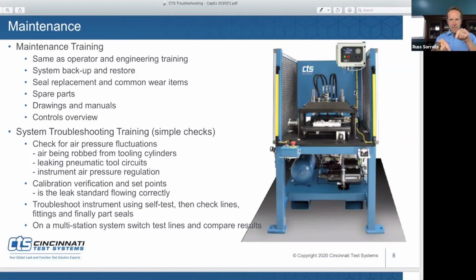Absolutely. Yeah, and it's just chasing it back. So often it's chasing it back, and one thing a CTS service person taught me is, if you have a dual station machine and a problem on one station and you're not sure if it's the instrument or the station, just take the airlines and swap them to the other station to see if the problem stays with the instrument or stays with the fixturing. That has saved me multiple times on dual station machines for sure. Absolutely. And if you look at the system troubleshooting training, simple checks, the very last bullet is exactly what you just said: on a multi-station system, switch test lines and compare results. Yeah. That will help you every time.